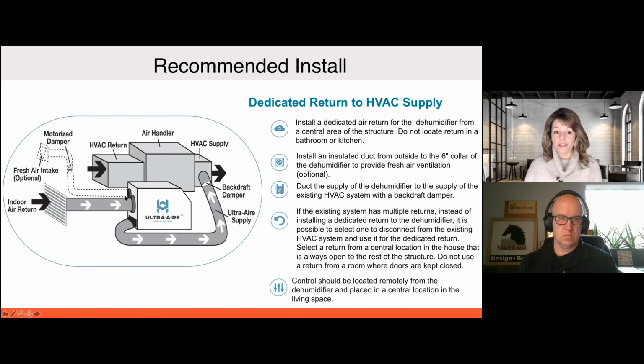So what's going to happen is, what we recommend is when the air conditioner shuts off and the RH is still too high, the dehumidifier comes on and dehumidifies the entire house. Now, you can also set it up where I don't care if the AC is running or not. I want the dehumidifier to run anytime that RH is above that set point. And you can set it up that way as well. But this is the most energy efficient way to set up a dehumidifier.